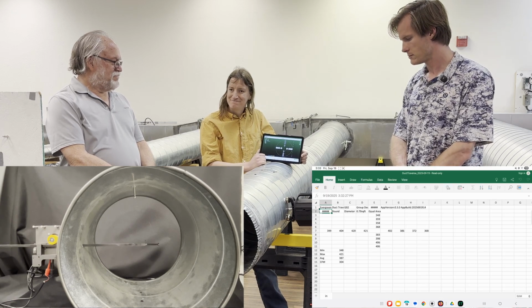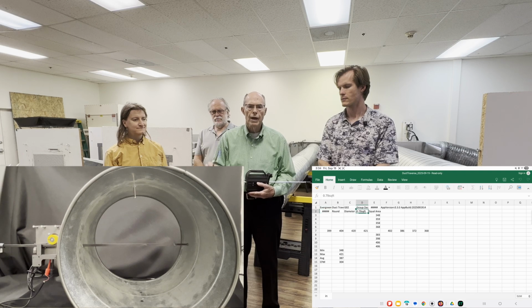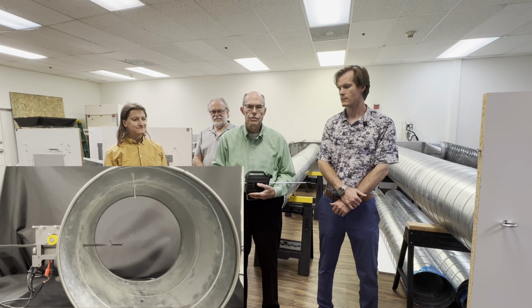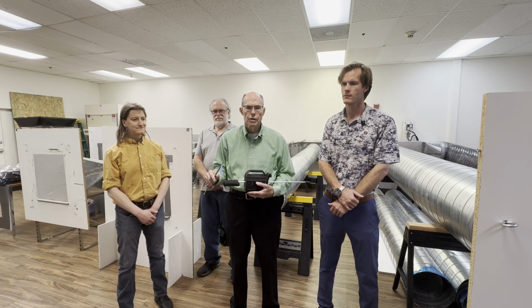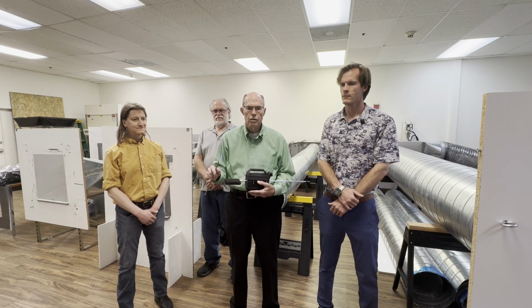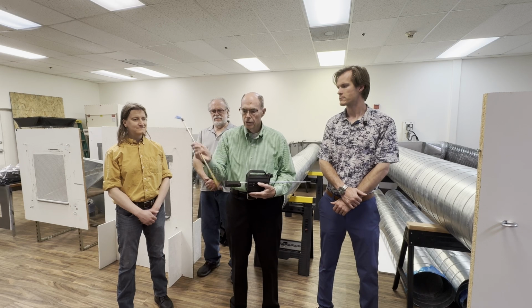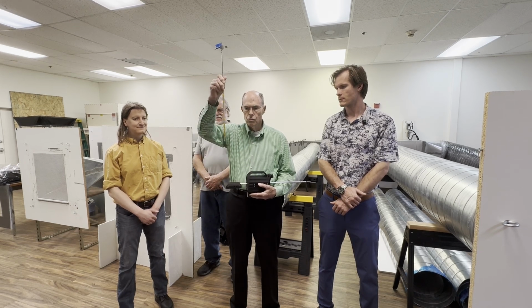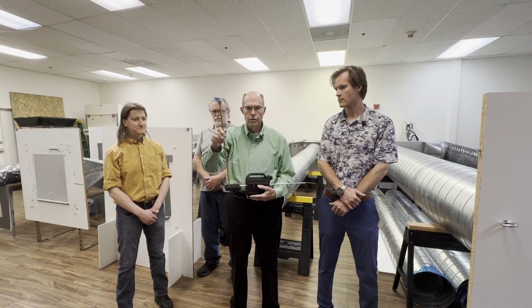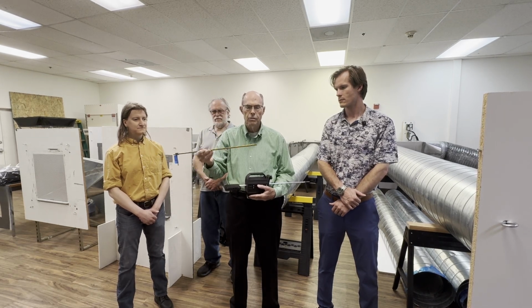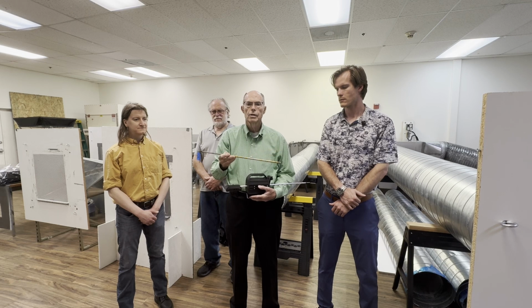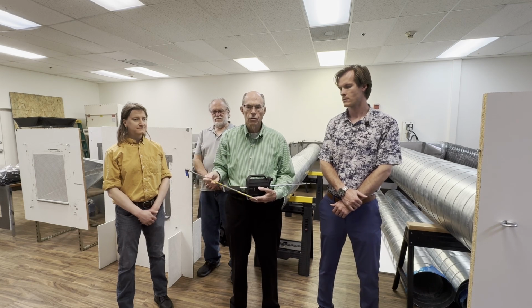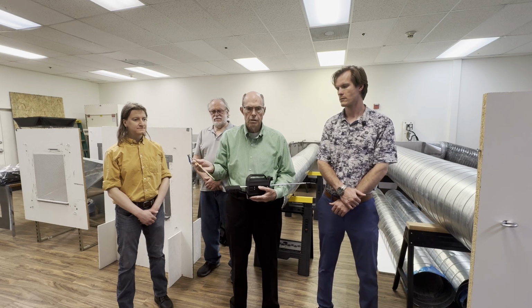I had to do thousands and thousands of duct traverses to make sure the capture hoods would match an NIST result. Here I was taping the probe, making sure it was perfectly vertical in the vertical axis and perfectly horizontal in the horizontal axis, comparing 2 out of 3 measurements and taking the 2 that were closest in order to get consistent results.